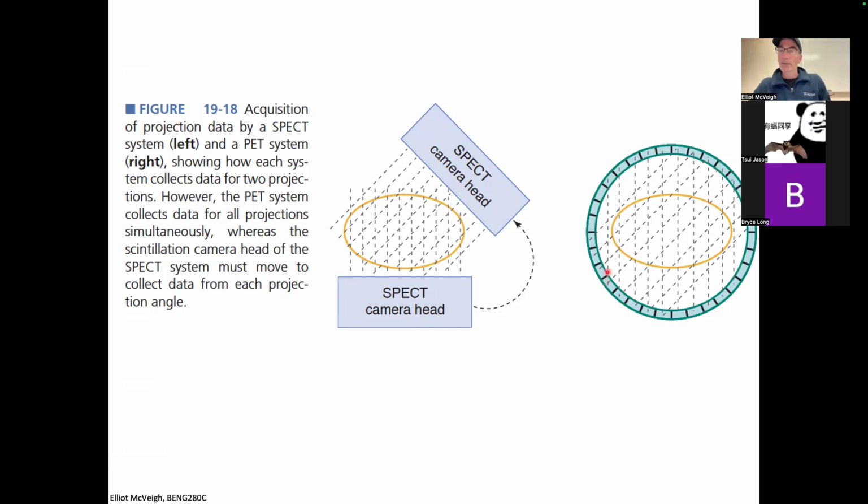And so when I'm creating a profile that is this projection, those two detectors go in and I just put 100 in that position. And then I move over here and now I have two new detector elements and say, how many coincident events did I get in those two? Say 50. So now I just plot that as a function of position along there. And that's how I reconstruct my projections.